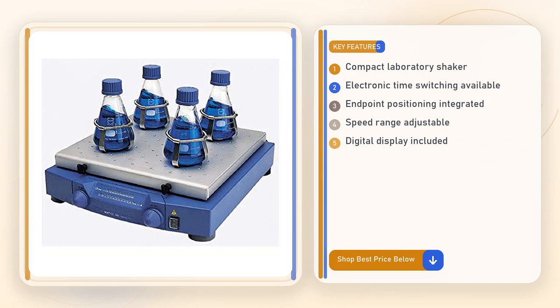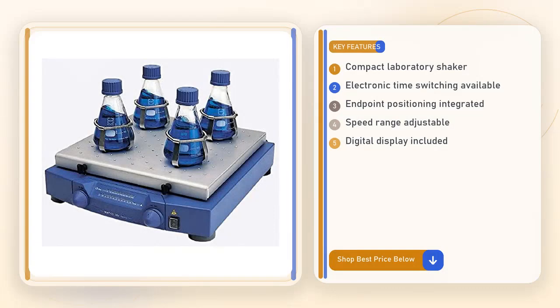The integrated endpoint positioning is another feature that sounds fancy, but becomes useful when you're pairing the shaker with a robotic sampling system. If your lab already uses an automated pipetting robot, the positioning point gives the robot a reliable reference to pause at the exact moment the shaking cycle ends. That means you can have a closed-loop workflow where the robot extracts a sample the second the agitation stops, preserving reaction conditions that would otherwise drift if you had to manually intervene. For a small academic lab that's still using manual pipettes, this might feel like overkill, but in a high-throughput setting it can shave minutes off each plate and reduce variability.